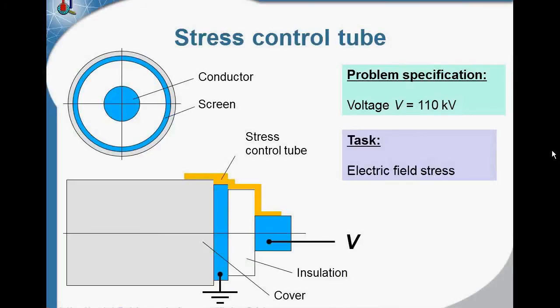Another problem with the electric field stress distribution is the case when you terminate the cable. Normally the electric field stress is distributed inside the insulation, but when you terminate the cable to connect it to terminals, you remove the cover, you remove the screen, you remove the insulation and connect the cable to the terminals. And in this place, high electric field stress occurs.